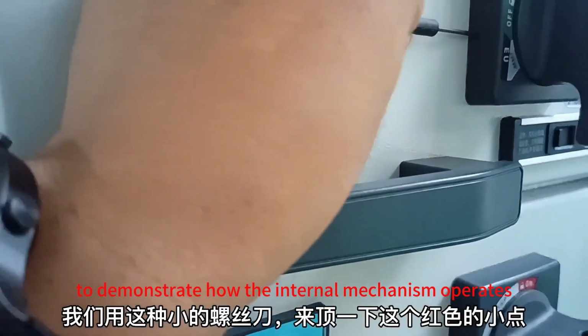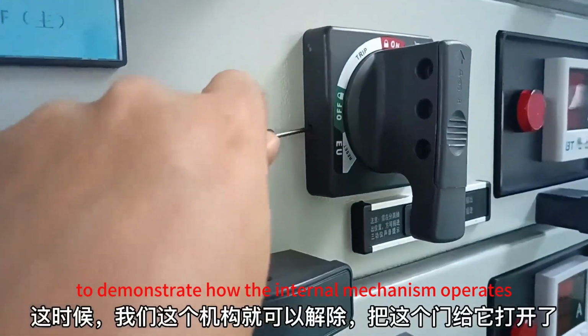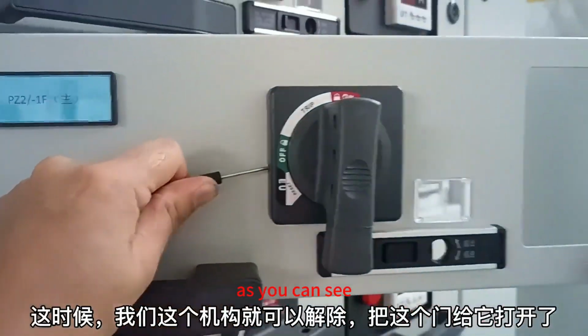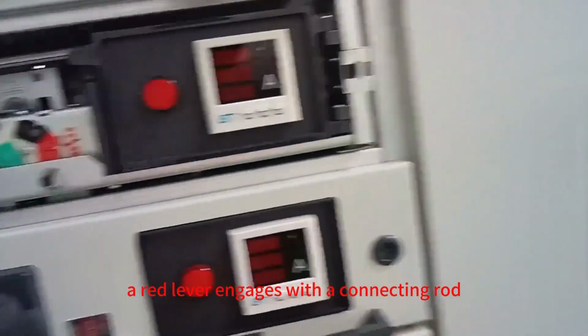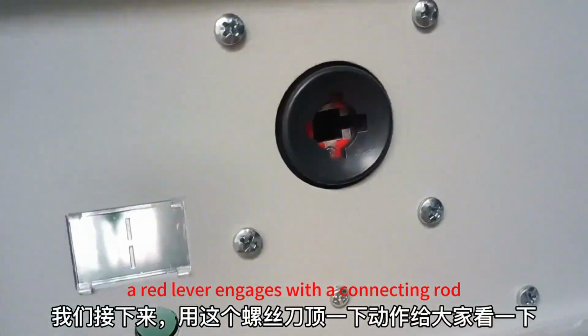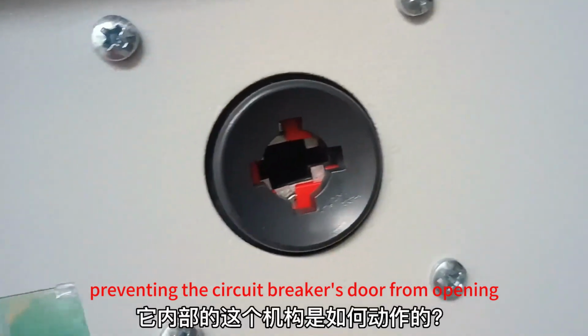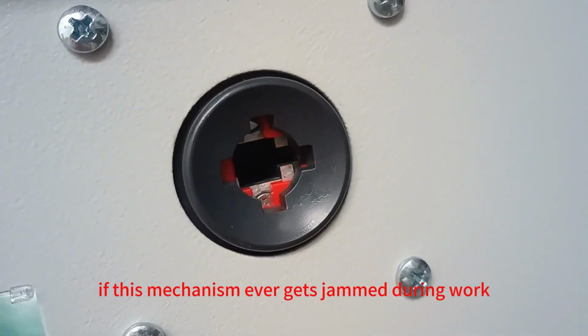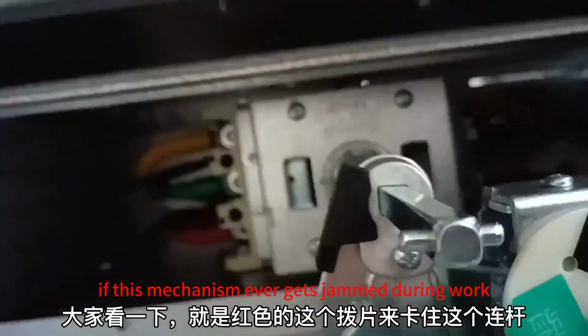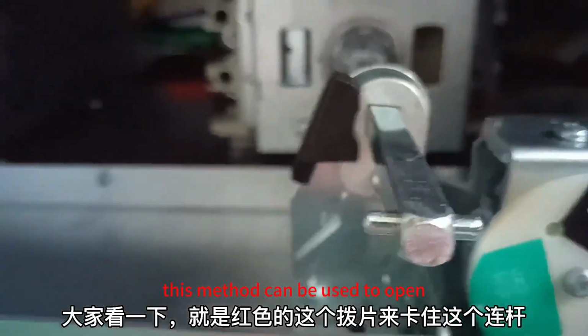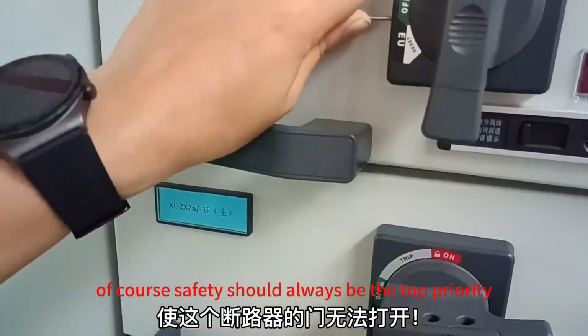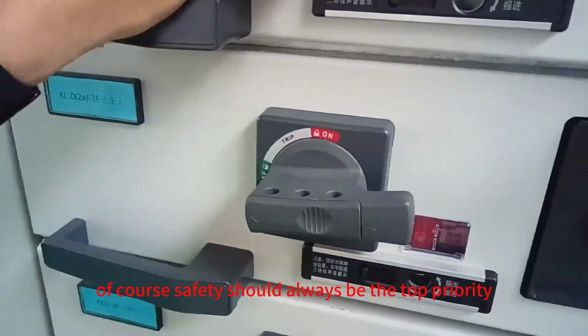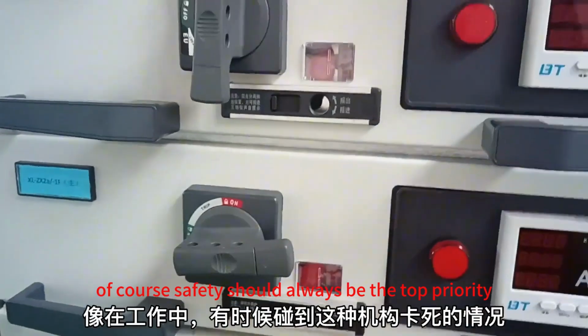Now, let's use the screwdriver to demonstrate how the internal mechanism operates. As you can see, a red lever engages with a connecting rod, preventing the circuit breaker's door from opening. If this mechanism ever gets jammed during work, this method can be used to open the door for maintenance. Of course, safety should always be the top priority.